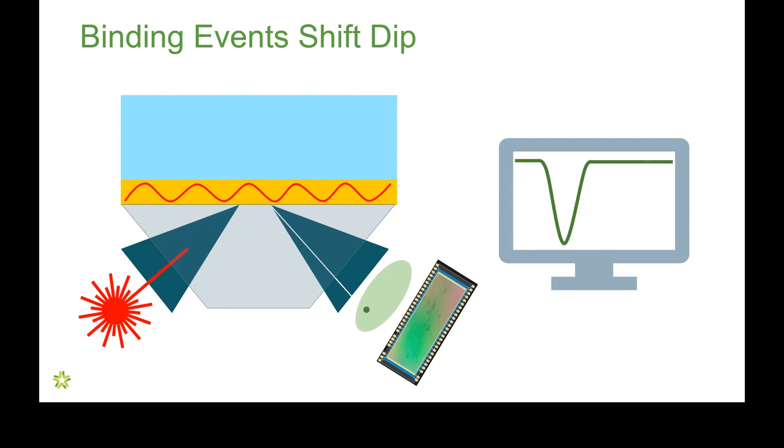For monitoring binding events, the exciting thing is that binding events also shift this dip. For example, if we attach ligands to the gold surface, the dip minima move to a higher angle. And then move even farther across this screen when analytes bind to the ligands. So, we can monitor how the analytes bind to the ligands and also how they unbind or dissociate from the ligands by tracking where that dip minimum occurs across the range of angles.